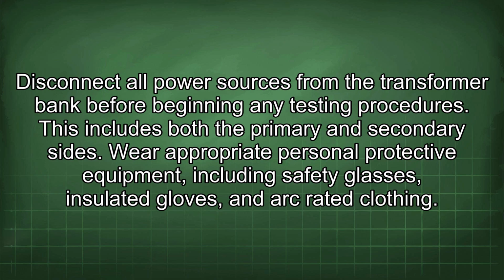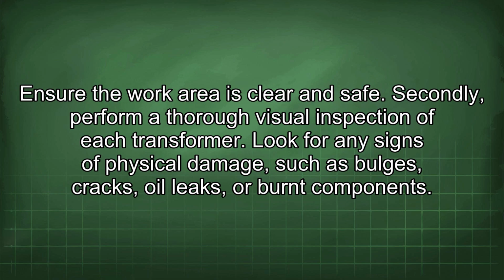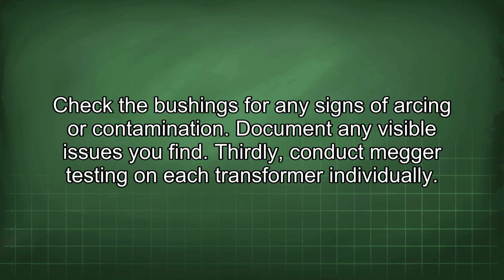Wear appropriate personal protective equipment, including safety glasses, insulated gloves, and arc-rated clothing. Ensure the work area is clear and safe. Secondly, perform a thorough visual inspection of each transformer. Look for any signs of physical damage, such as bulges, cracks, oil leaks, or burnt components. Check the bushings for any signs of arcing or contamination. Document any visible issues you find.